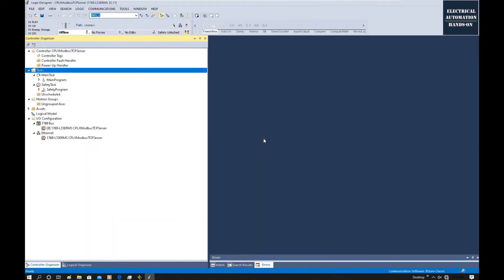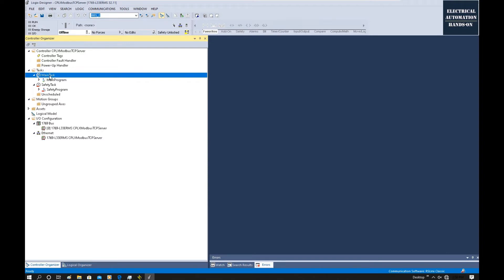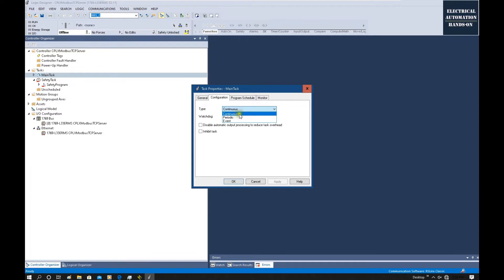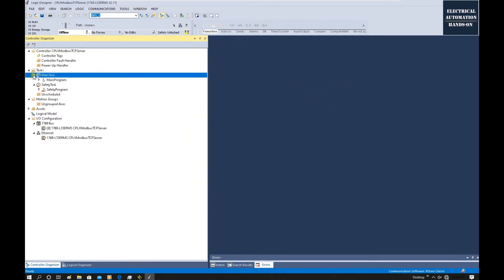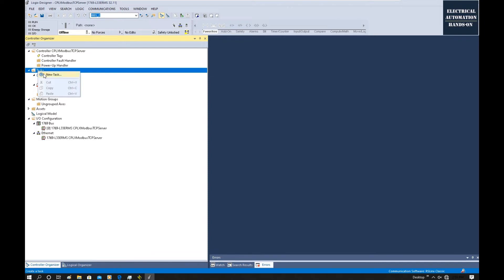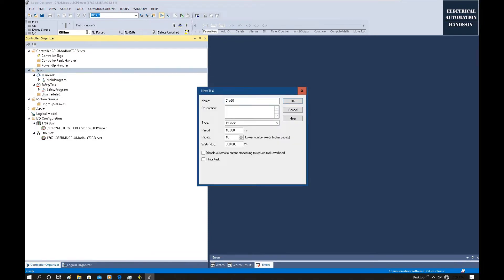First, let's create a periodic task. If we look at the existing main task, that is a continuous task. All our normal programs will be under this task. But as recommended in the manual, to implement the Modbus TCP server AOI, we should create a periodic task. Right-click the task, click New Task. We can create one task with a period of 20 milliseconds. Here, set the period to 20 milliseconds and make sure we select Periodic. This task will run every 20 milliseconds.